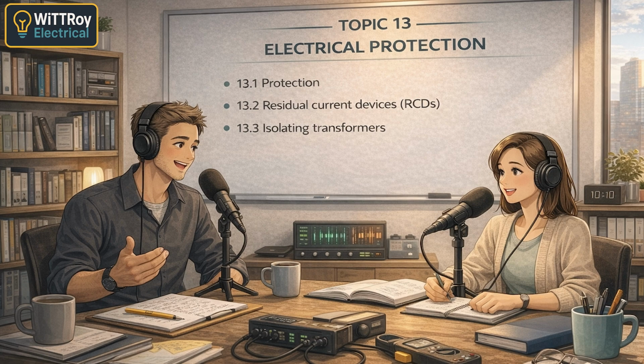So excess current protection is mainly about fire prevention. Fire prevention and equipment protection, yes. Not really about people then. Good question. No. Excess current protection protects cables and equipment, not people directly. That's what RCDs are for. Exactly. We'll get to those later.